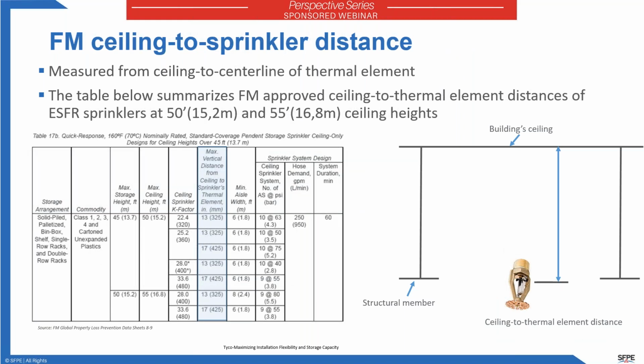As I noted previously, FM measures the sprinkler location from ceiling to center line of thermal element. And I have a chart here that's taken from the latest edition of FM 8-9. You can see that FM 8-9 in this particular table focuses on ceiling heights of 50 and 55 feet. FM has approved protection schemes with ESFRs 22, 25, 28, and the 33.6 at 50 feet, and has a couple of protection schemes with the ESFR 28 and JCI's new ESFR 33.6 sprinkler at 55-foot ceiling. And so looking at the column that's highlighted in blue, you would see that depending on the sprinkler type, there are differences in the distance from ceiling to sprinkler's thermal element, which can be pretty significant.